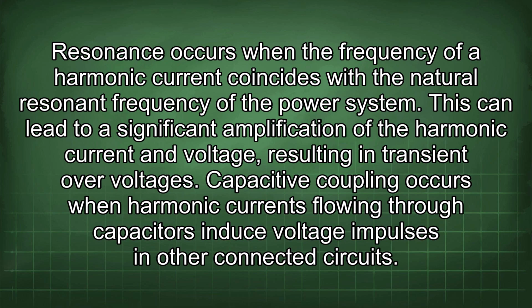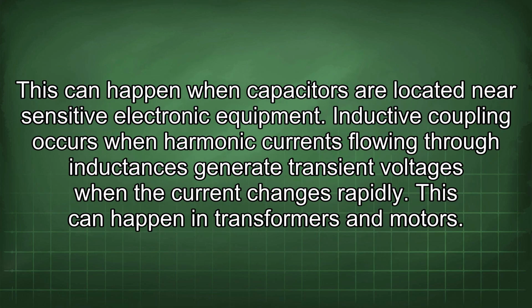Capacitive coupling occurs when harmonic currents flowing through capacitors induce voltage impulses in other connected circuits. This can happen when capacitors are located near sensitive electronic equipment. Inductive coupling occurs when harmonic currents flowing through inductances generate transient voltages when the current changes rapidly. This can happen in transformers and motors.